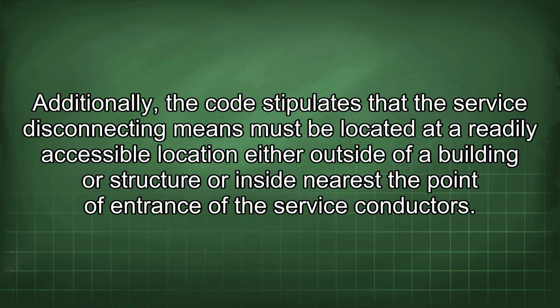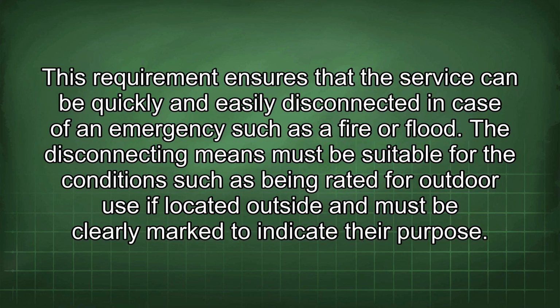Additionally, the code stipulates that the service disconnecting means must be located at a readily accessible location either outside of a building or structure or inside nearest the point of entrance of the service conductors. This requirement ensures that the service can be quickly and easily disconnected in case of an emergency such as a fire or flood. The disconnecting means must be suitable for the conditions, such as being rated for outdoor use if located outside, and must be clearly marked to indicate their purpose.